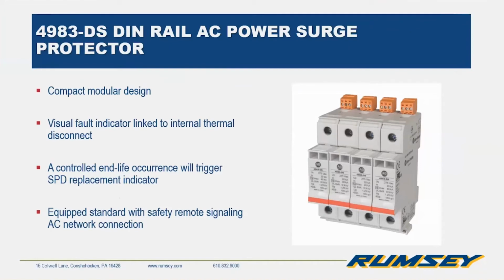So now we're going to move on to the 4983 bulletin of products, which are surge and power quality products. So the 4983DS is a surge protection product. They have a compact modular design, so you can get these from anywhere from a single pole to a 4-pole device with a visual fault indicator. So you could know remotely when the ability to protect has exceeded its lifespan. So if it gets hit with a surge, you may need to replace this, and that will give you the ability to know that's a requirement now.